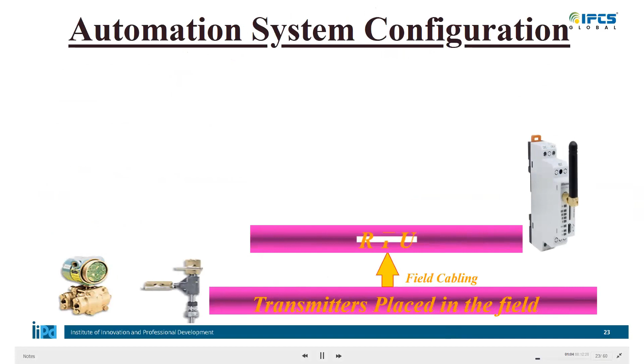For example, you have a system with nearly 500 inputs and 500 outputs, and this input and output is spanned across a very long distance. You have a part of your machine nearly 200, 300 meters away, with the control panel in your control room. If you want to wire 100 inputs and 100 outputs from the field unit to your PLC, you'd have to lay at least 300, 400 wires.